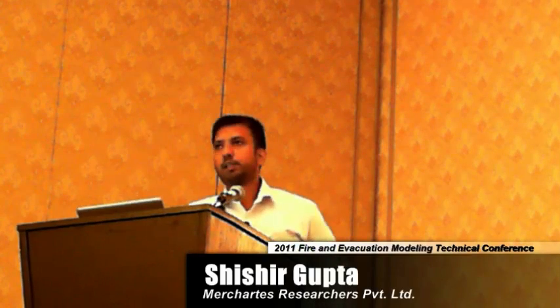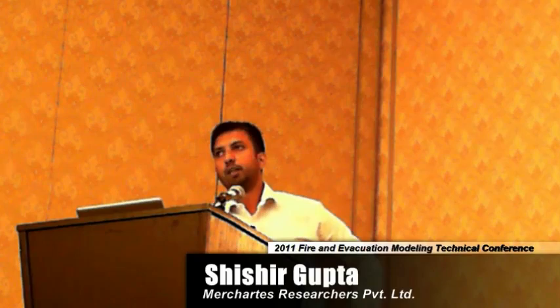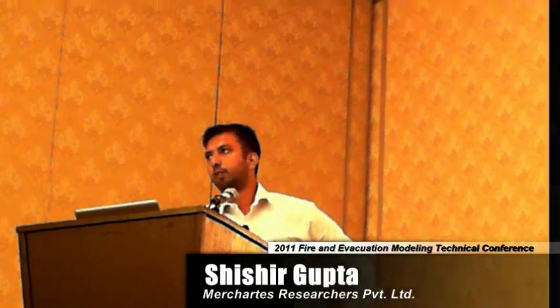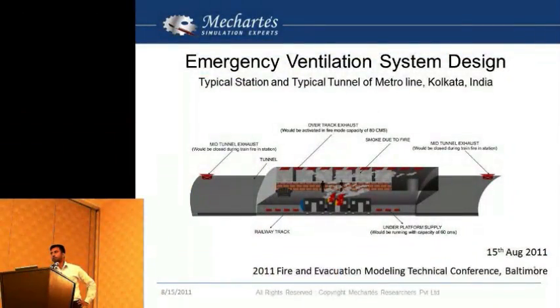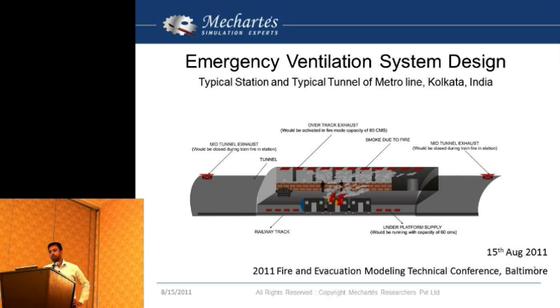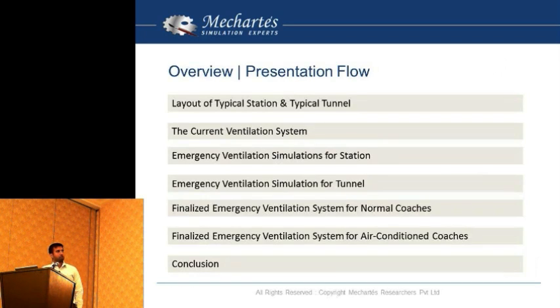I'm going to talk about this case study of a metro station in which FDS was used to come up with a smoke ventilation strategy. This is a retrofit job. The metro line has been existing for 30-40 years, but the initial ventilation system was not designed to take care of smoke ventilation — it was only for physiological requirements. So there were a lot of constraints, which make the project more interesting.